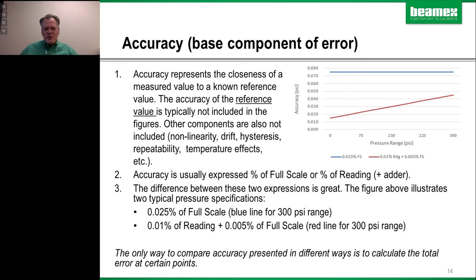And then if we had a different statement, 0.01% of reading and 0.005% of full scale, that's the red line. So see how it has that base error at 0, 0.015 psi, and then it moves up at a slope. So the point of these two statements, the full scale versus the percent of reading and base error, is the red line is like twice as accurate as what's stated by the blue line. But in any event, the only way to compare accuracy statements is to actually calculate the engineering units that you're working in. So notice that this graph is from 0 to 0.08 psi. To do a true comparison, you have to use these examples and calculate to the engineering units that you're working in. So this is a way for you to interpret how accurate pieces of equipment are.